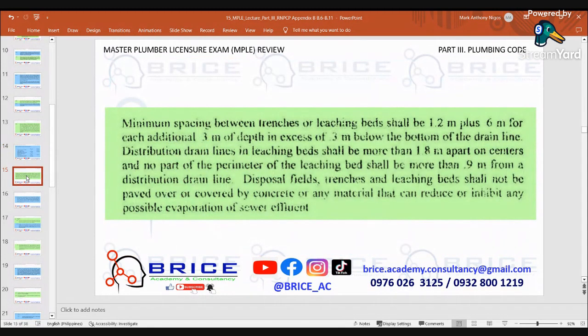Okay, minimum spacing between trenches or leaching beds shall be 1.2 meter plus 6 meter for each additional 3 meter depth in excess of 3 meter below the bottom of the drain line. Distribution drain lines in leaching bed shall be more than 1.8 meter apart on centers, and no part of the perimeter of leaching bed shall be more than 0.9 meter from the distribution line.